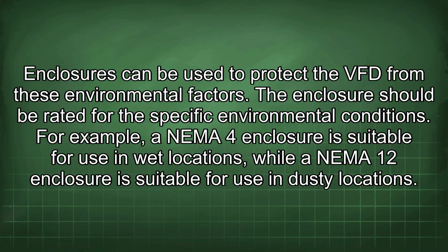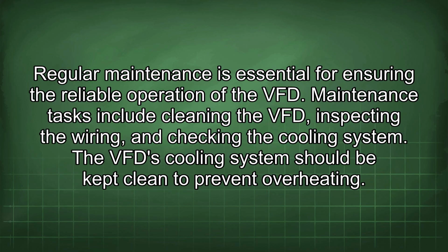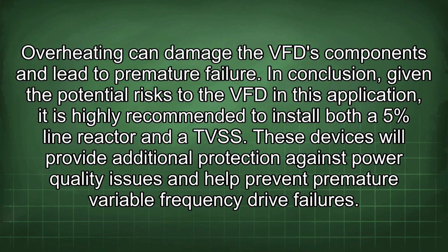in dusty locations. Regular maintenance is essential for ensuring the reliable operation of the VFD. Maintenance tasks include cleaning the VFD, inspecting the wiring, and checking the cooling system. The VFD cooling system should be kept clean to prevent overheating. Overheating can damage the VFD components and lead to premature failure.